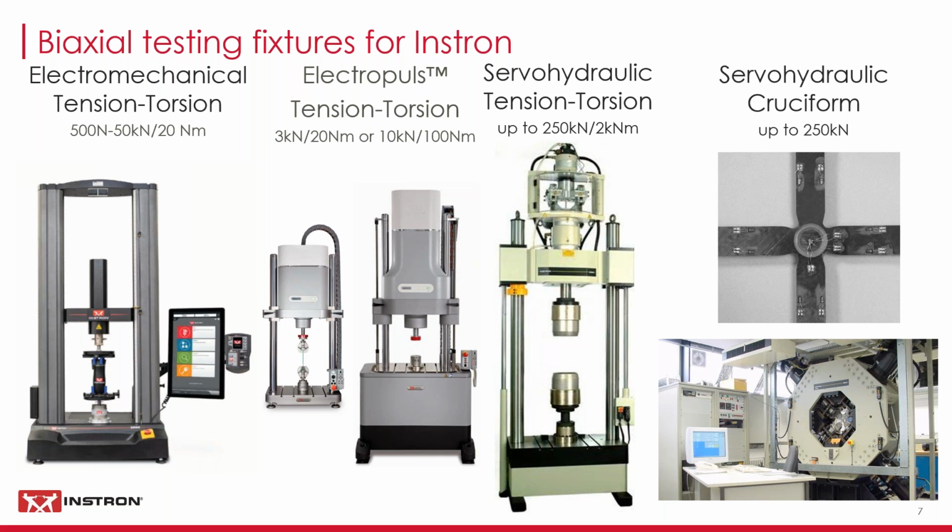Then moving up on the dynamic side, our Electropuls range of electrodynamic machines requiring no oil, forces of up to 10 kilonewtons, torques of up to 100 Newton meters. Also smaller capacities, 3 kilonewtons, small capacity.